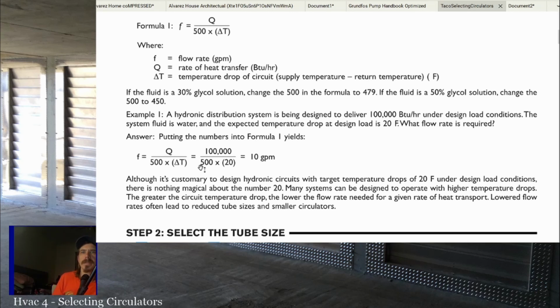So in this example, we'll look at a hydronic distribution system being designed to deliver 100,000 BTUs under design load conditions. The system fluid is water, and the expected temperature drop at design is 20 degrees. What's the flow rate required? So if we wanted a 20-degree temperature drop for a 100,000 BTU system, then we're going to do F equals 100,000 divided by 500 times 20, which is going to be 10,000, and that's going to be 10 GPM. So in this case, we want a pump that can handle 10 GPM.